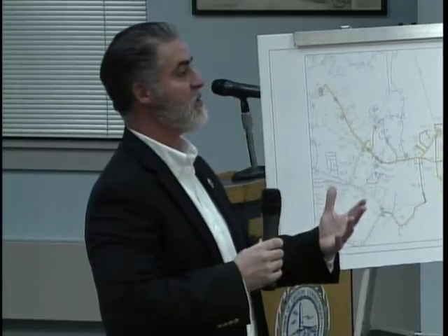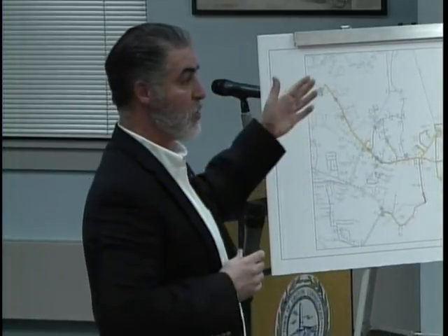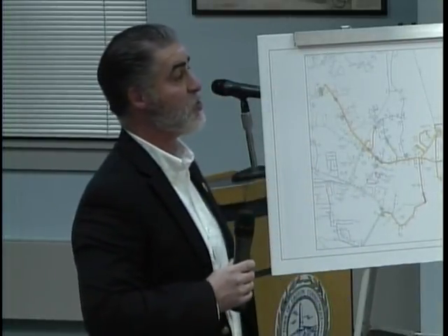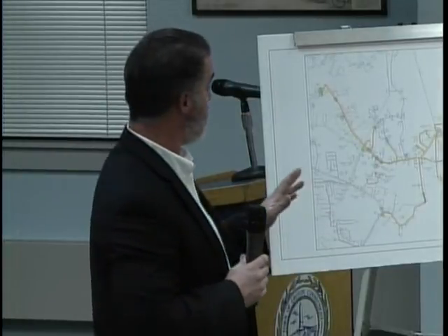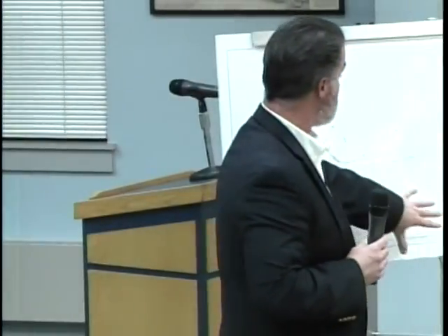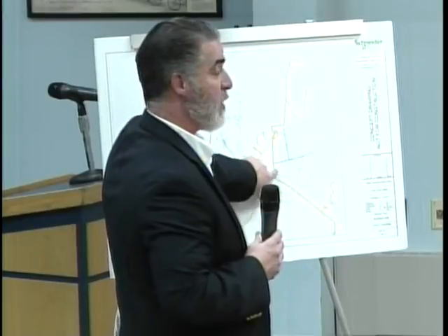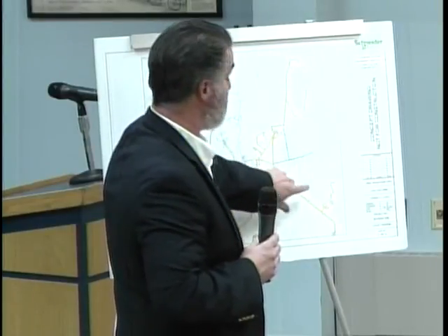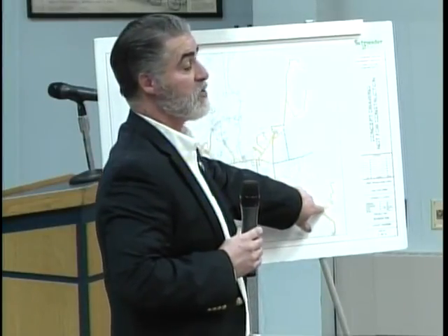There's analysis that has to go on to determine those points, and that's what Schneider is doing behind the scenes. They're determining, okay, there's 2 generators here, where's 1.5 megawatts of load in this general area to be able to start that generator. You have to load it at least 1.5 megawatts.